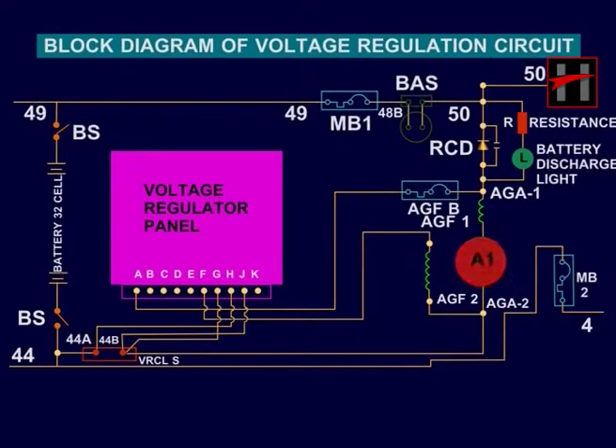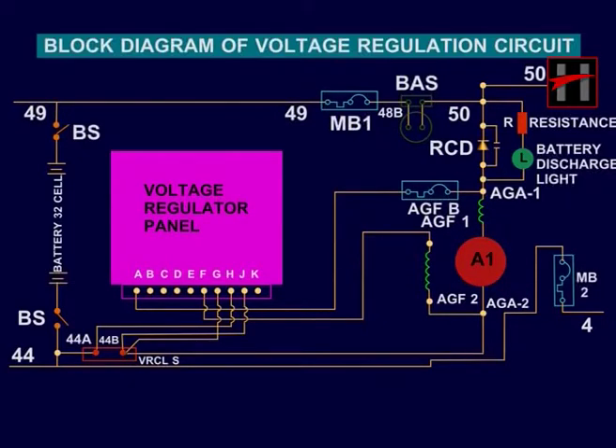The average current in the generator field is determined by the ratio of on time to off time. On time is fixed by the circuitry of the regulator, but off time is determined by the pulse rate from the regulator card. As the generator voltage increases, the pulse rate decreases; as the generator voltage decreases, the pulse rate increases.